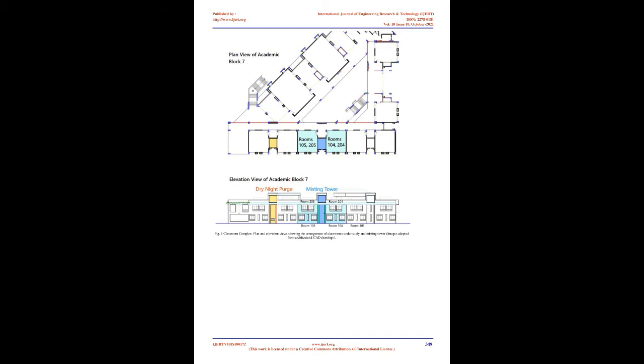Results. A number of tests and measurements were conducted during the period of May-June 2016, of which we present here representative data from May 30th to 31st, 2016 represented in Fig. 4. The trends for the rest of the testing period were also similar. In the tests depicted in this Fig, dry night purge is switched on starting at 2200 hours at night until 0500 hours next morning to bring classroom temperature and humidity close to the ambient conditions. Later, the PDEC system is started with misting at a pressure of 1000 psi from 0500 hours in the morning so as to preempt the effect of incident sunlight and subsequent rise in temperature. The PDEC system remains on until 1700 hours in the evening.